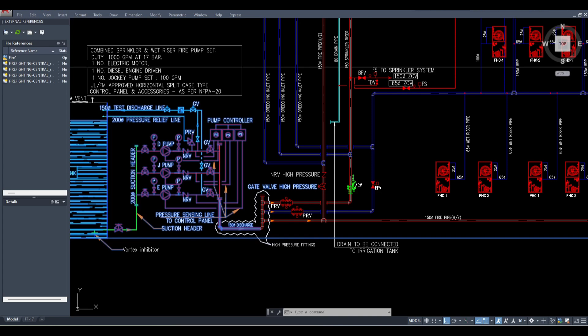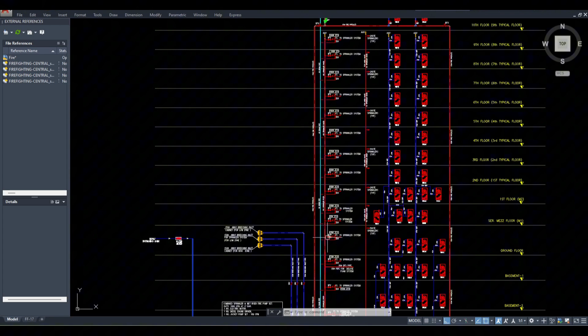No, when the fire system designer is designing the fire system, they consider one fire at one place. They cannot consider that everything is operating at the same time. These fire sprinkler systems are designed just to contain the fire for some certain time. It is not meant to suppress the fire completely, or eliminate it completely. Elimination of the fire is the duty of the firemen manually, it cannot be done automatically, because fire behaves in an unpredictable manner, it can flash from here to there.